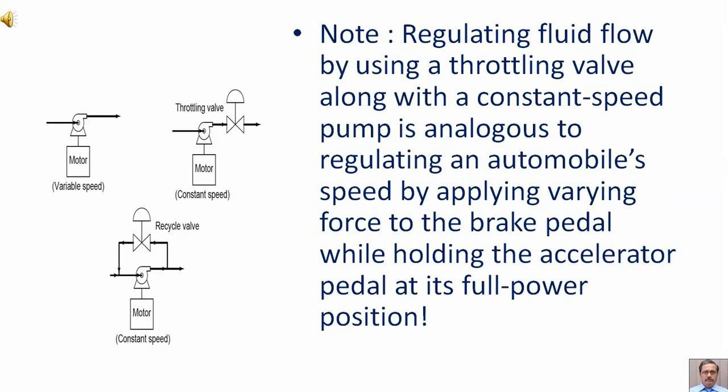Note: regulating fluid flow by using a throttling valve along with a constant speed pump is analogous to regulating an automobile's speed by applying varying force to the brake pedal while holding the accelerator pedal at its full power position.